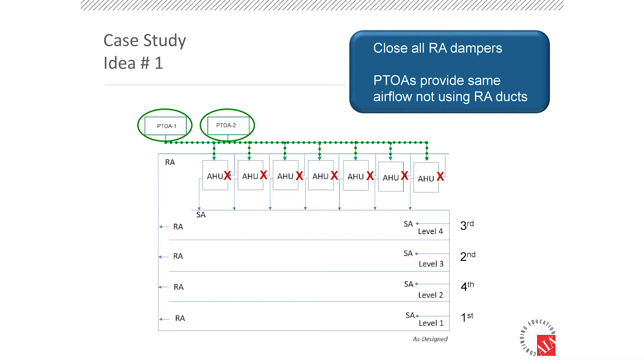The first idea was, hey, since everything's dirty, can we just close all the return dampers and feed the whole place with supply, so that none of the return ducts would be open, and we can get through tab this way, at least get air everywhere. Maybe we can feed what would have come through the return to those air handler units from these two outside air handler units that feed them. Can that work? Can we do that?